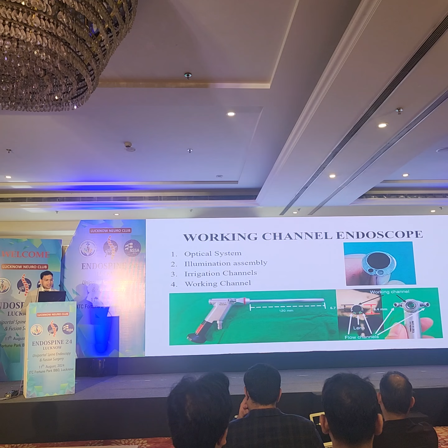Then in the sides we have the irrigation channels. In the center, the small one is the light, that is the illumination assembly. Now the working channel endoscopes can be of different types depending upon where we are operating. We can be operating on the cervical spine, thoracic spine, or the lumbar spine. So the length of the endoscope in lumbar spine can be from 150 to 180 mm. The outer diameter can range from 5 mm to 10 mm. The inner diameter may range from 3 mm to 8 mm. The irrigation channel diameter is usually 1.5 into 1 mm.